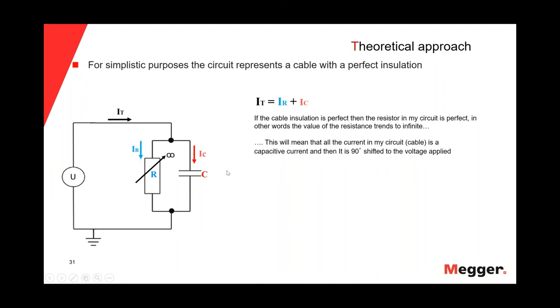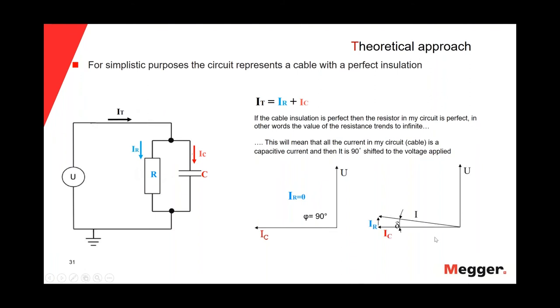If we do the phase diagram of this circuit, we will see that the voltage and the current are separated by an angle of 90 degrees, with the resistive current equal to zero. Now, if we don't have a perfect insulation, the value of the resistance no longer trends to infinite, and we will start to see some resistive current going through the resistor. In that case, the phase diagram changes, and we now have a small component of the resistive current.